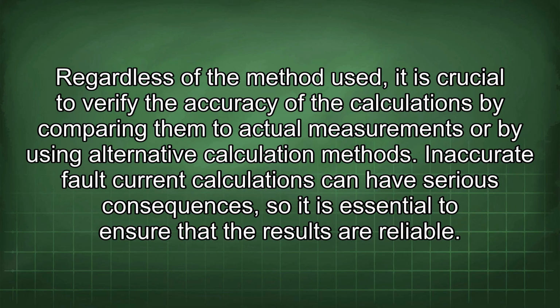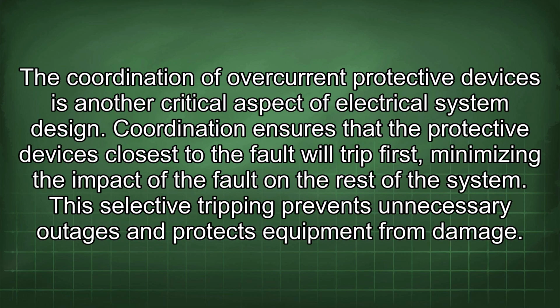Regardless of the method used, it is crucial to verify the accuracy of the calculations by comparing them to actual measurements or by using alternative calculation methods. Inaccurate fault current calculations can have serious consequences, so it is essential to ensure that the results are reliable. The coordination of overcurrent protective devices is another critical aspect of electrical system design. Coordination ensures that the protective devices closest to the fault will trip first, minimizing the impact of the fault on the rest of the system. This selective tripping prevents unnecessary outages and protects equipment from damage.